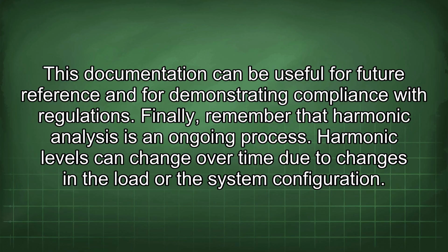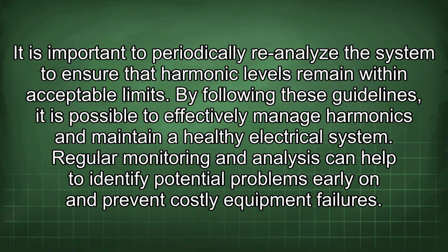Finally, remember that harmonic analysis is an ongoing process. Harmonic levels can change over time due to changes in the load or the system configuration. It is important to periodically reanalyze the system to ensure that harmonic levels remain within acceptable limits. By following these guidelines, it is possible to effectively manage harmonics and maintain a healthy electrical system.